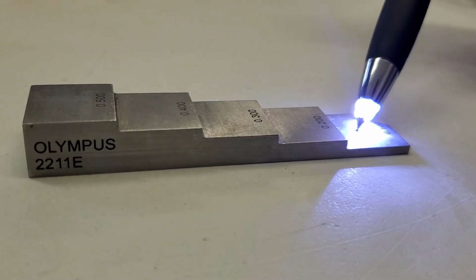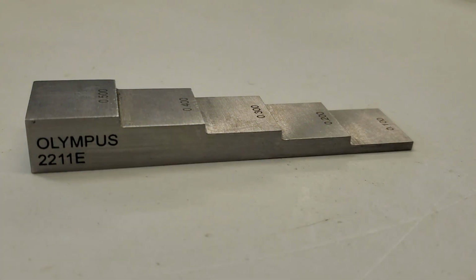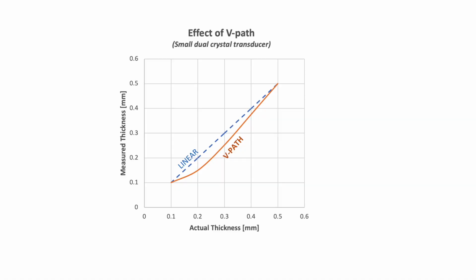Let me show you the practical effect of a V-path error. Here I took a very small dual element transducer and I actually calibrated it on the 0.1 and 0.5 ends of a step wedge. Now, you wouldn't typically use a transducer that small to measure a range that big, but let's say that's the way you set it up. This is a really good way to illustrate V-path error. My calibration points are at the 0.1 inch and 0.5 inch ends of the step wedge. You can see here, they line up perfectly, of course, because that's where I calibrated. It's the stuff in the middle that gets thrown out by a V-path error.